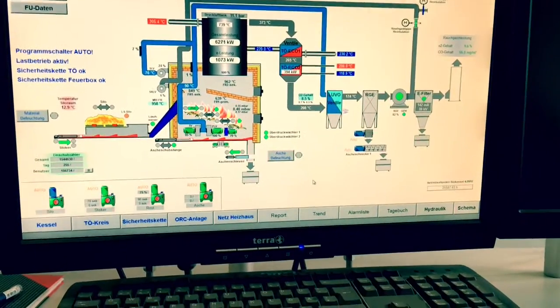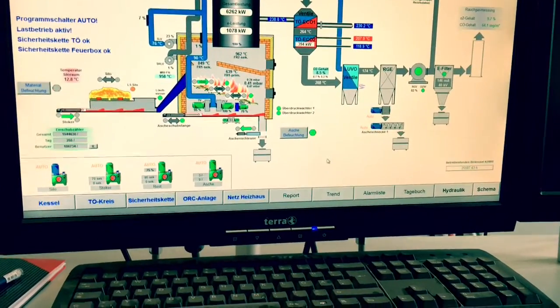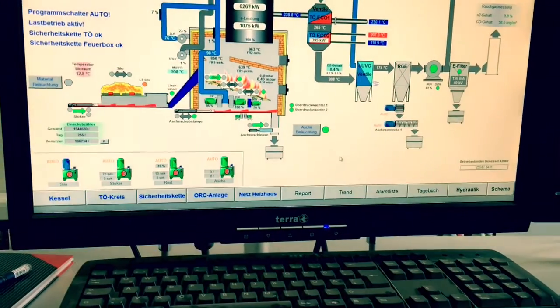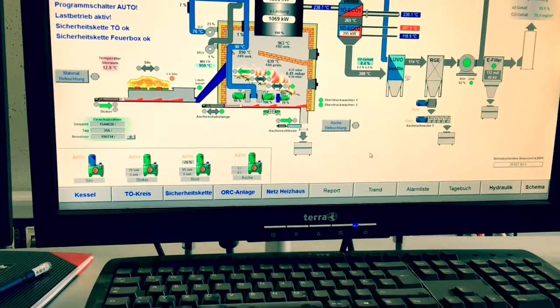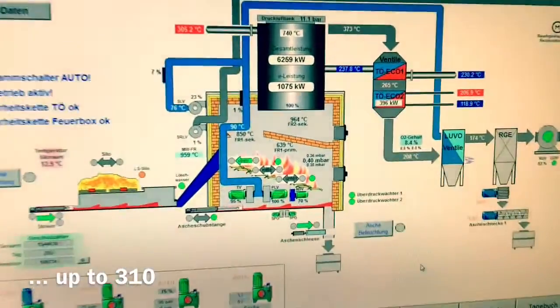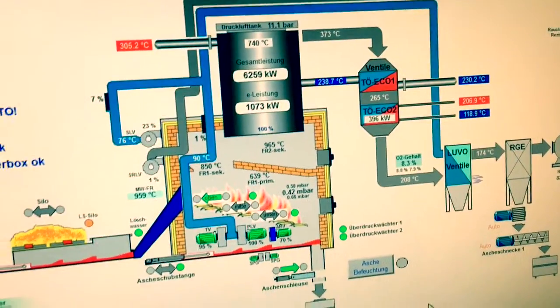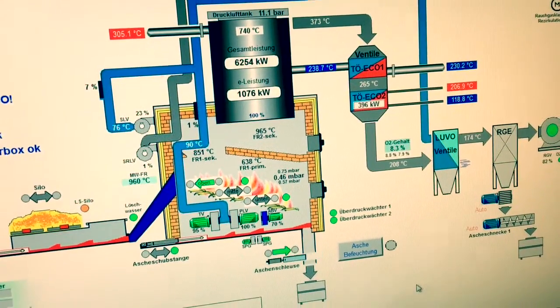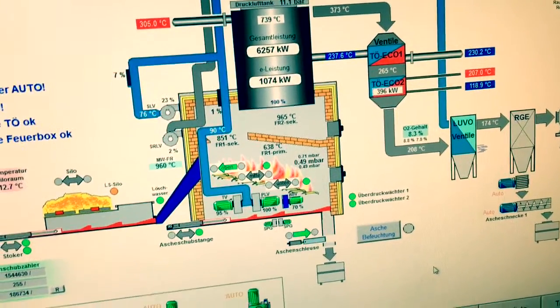On this screen, the central processes are visualized. With the combustion of the biomass, we heat a special thermal oil up to 310 degrees Celsius. This oil is then pumped into the power plant, where a second special oil is vaporized, which drives the turbine with high pressure.